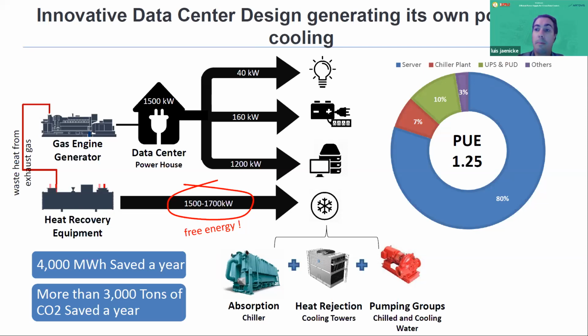Heat rejection equipment and pumps are still there. It's still a chiller plant. So around 100 kilowatts or even below will still be part of the chiller plant electrical consumption. But in this case, it's no longer 30%. We are talking around 7% of the overall consumption of the data center will go for the chiller plant. So between the 1.4 megawatt of the IT load plus 100 kilowatt of the chiller plant, I need to provide 1.5 megawatts of electricity to this data center.